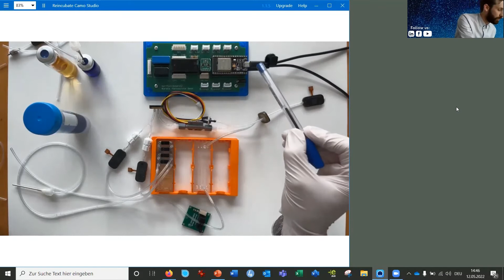So what you can see here are some components you've seen on my last slide. Here are two, or rather three, of our pumps, a liquid flow sensor by Sensirion, a Honeywell drug pressure sensor, microfluidic chips in the handling frame by Microfluidic ChipShop, also some valves by Memetis, normally closed shape memory alloy valves, and some other components like an optical sensor, check valves, a pulsation damper, and the engine of the whole setup, a microcontroller-based circuit board running and reading the components.